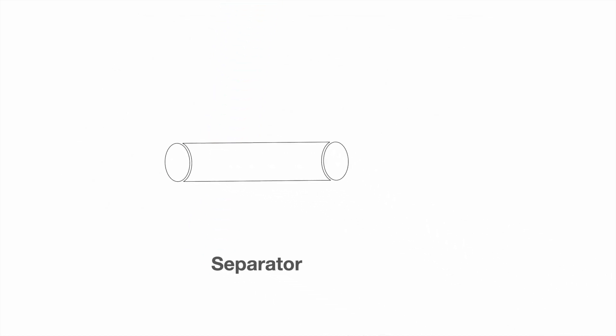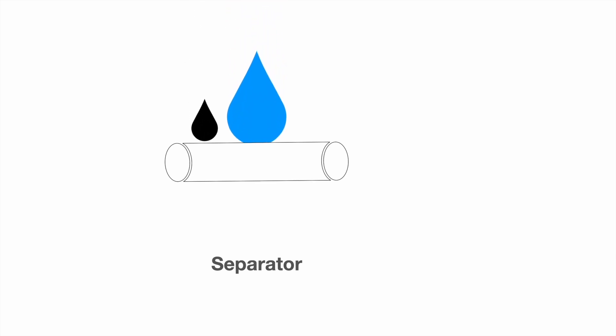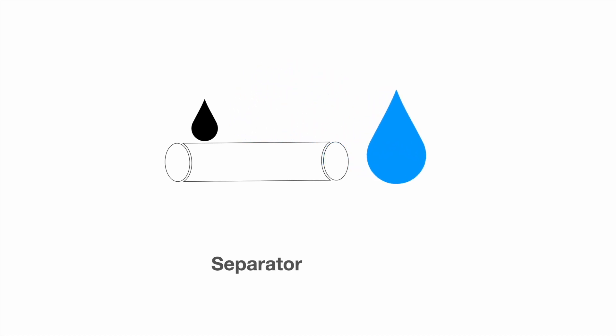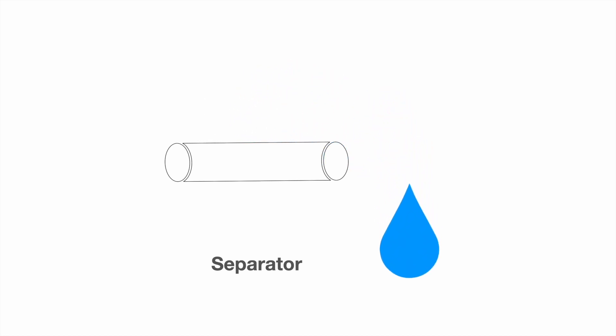Teflon-coated separator cartridges are employed as the second stage in filter separator vessels. Their sole function is to repel coalesced water drops produced by the first stage cartridges while allowing hydrocarbon fluids to pass through. Water drops settle into the filter separator sump and are not carried downstream.